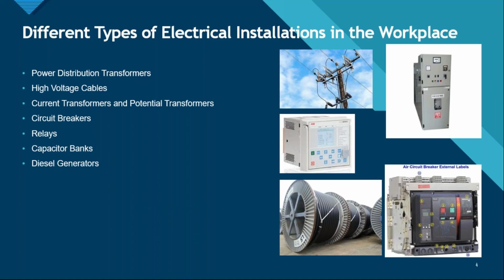Then there are current transformers and potential transformers. Basically, current transformers and potential transformers make it easy for a relay or a meter on your electrical panel to measure the current or the voltage, right? When there is current or voltage passing through an electrical room, it is very high in rating. And we have relays, maybe electromechanical relays or electronic relays, which work on very low voltages, right? Like for example, your phone has very low voltage. If that high rating of current or voltage passes through an electronic system, it is going to damage the electronic system severely, so it needs to be stepped down to be passed on to your relay or to the circuit breaker.